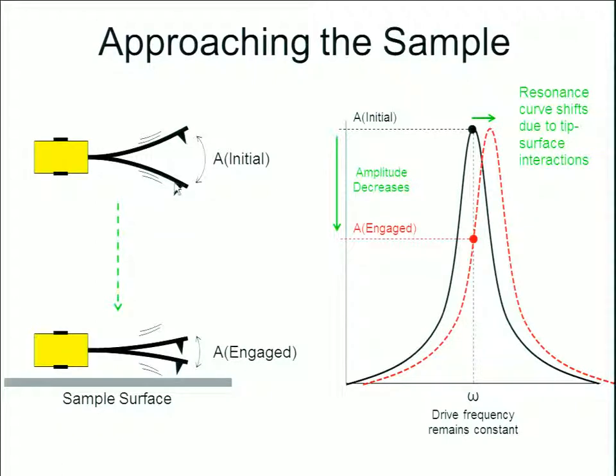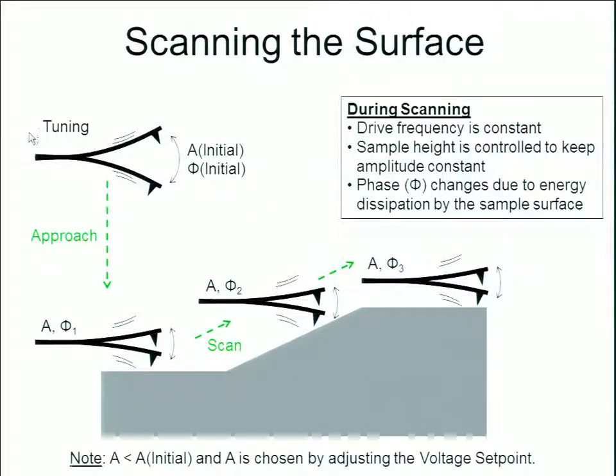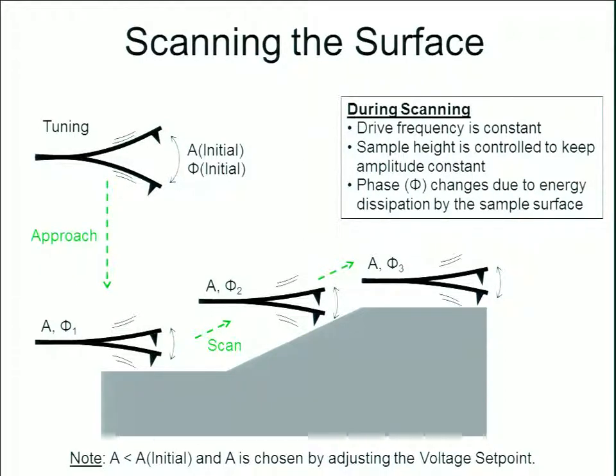We set the drive frequency in air, engage the sample, and observe a shift — in this case, a shift in amplitude. The shift is due to tip-surface interactions. The piezoelectric is still controlled by the feedback loop in order to maintain a constant height, trying to keep that amplitude constant. Every time it changes, the feedback loop sends a signal to the piezo to move the sample up or down accordingly.